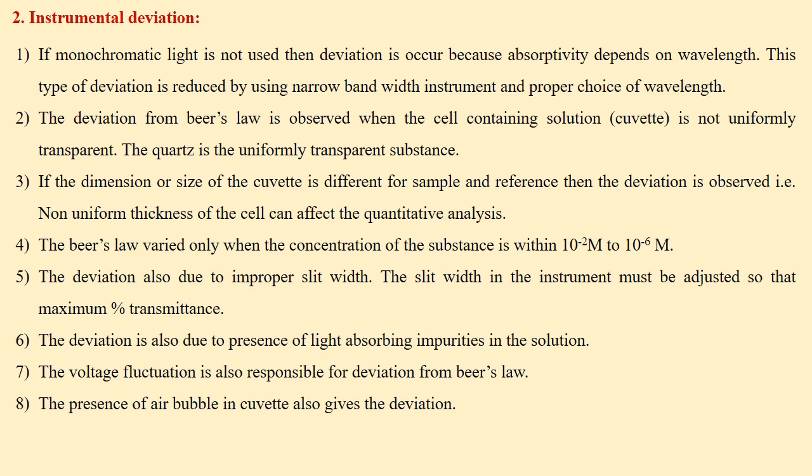Another reason is that the measurement also depends on the range of concentration. Some instruments operate only within 10 raised to minus 2 molar to 10 raised to minus 6 molar concentration. Deviation is also caused sometimes by improper slit width. The slit width in the instrument must be adjusted so that there is a maximum percentage of transmittance.